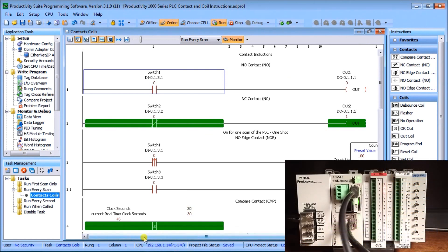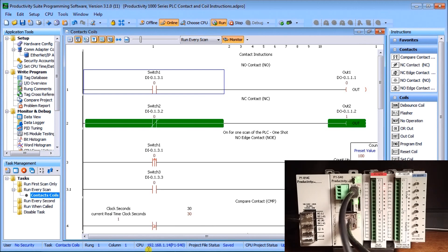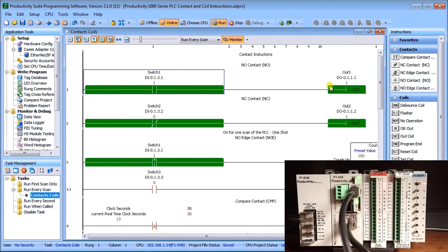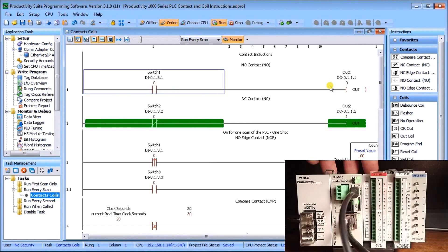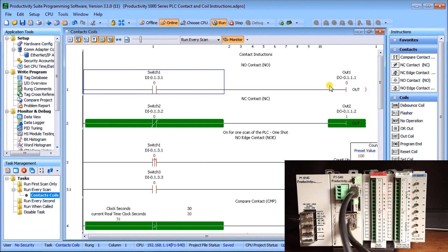Now let's look at our PLC — I'm connected here's my CPU, connected through my Ethernet port. There are my output card, my I/O, and my simulator for the I/O that we'll be using. We have switch one going to output one. If I turn on switch one, sure enough that output turns on, and if I turn that switch off, the output comes off. We are in run mode and it's doing our scan of our program.